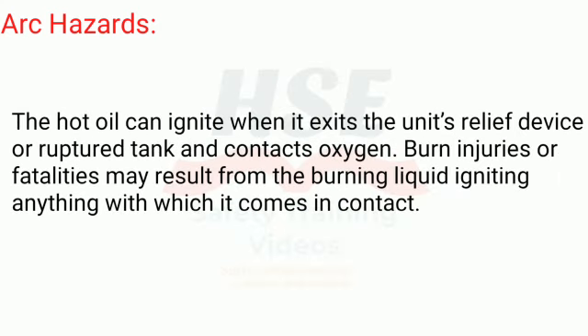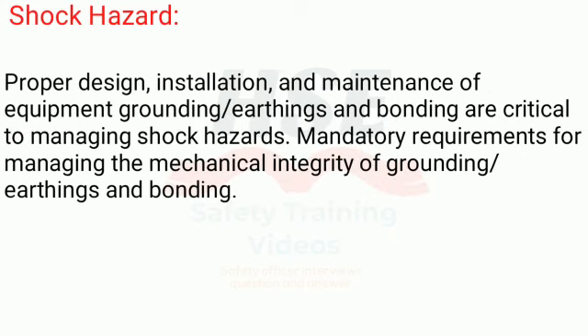The hot oil can ignite when it exits the unit's relief device or ruptured tank and contacts oxygen. Burn injuries or fatalities may result from the burning liquid igniting anything with which it comes in contact. Shock hazard. Proper design, installation, and maintenance of equipment grounding, earthing and bonding are critical to managing shock hazards.